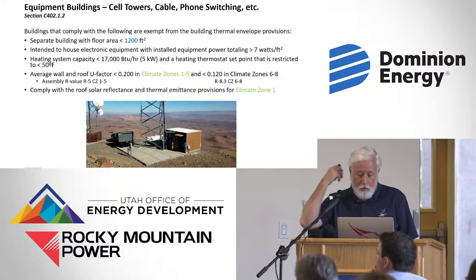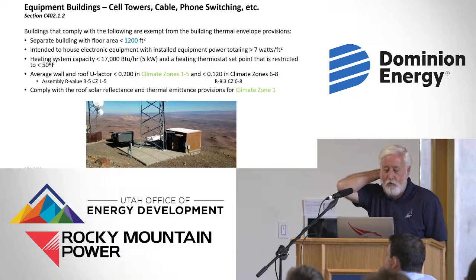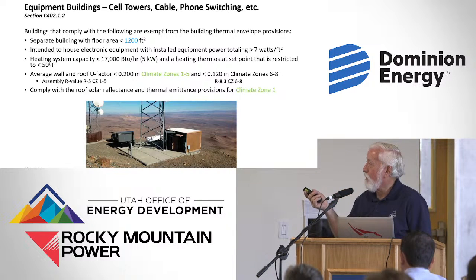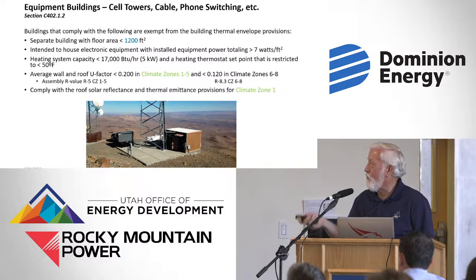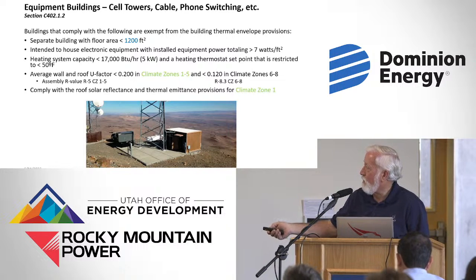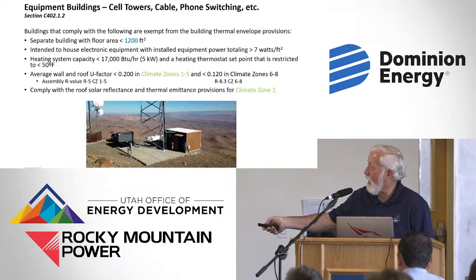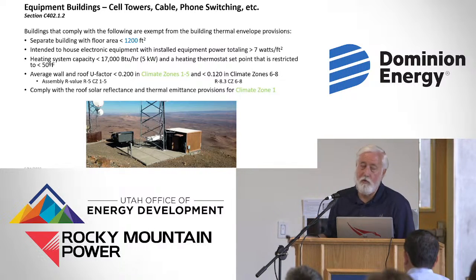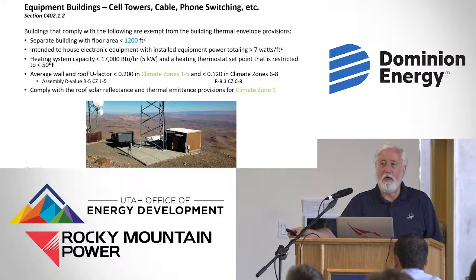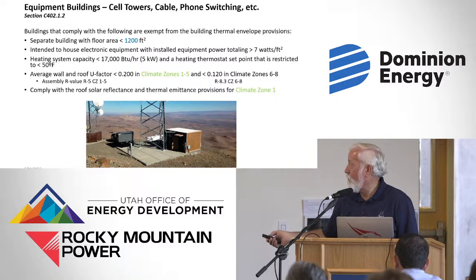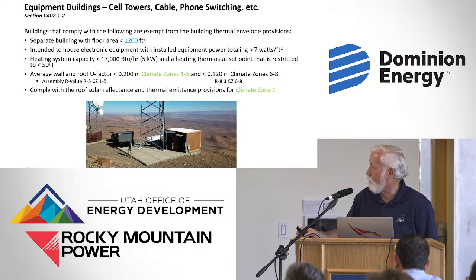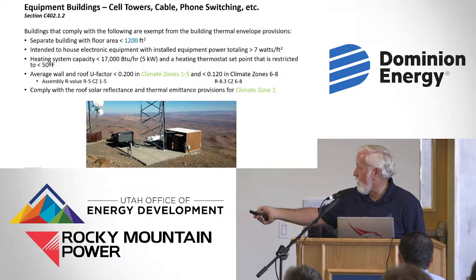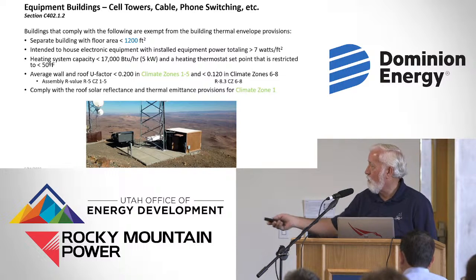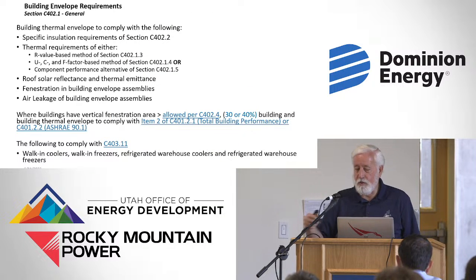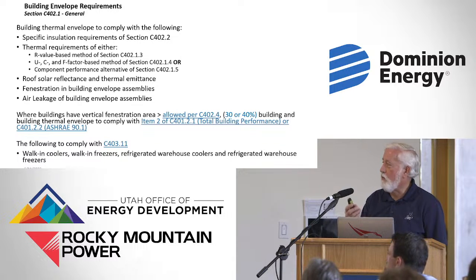Equipment buildings for cell towers and such, phone switching - basically what they're saying is they don't need much heat, they generate a lot of heat. Depending on your climate zone, an average wall and roof U-factor of 0.2 is basically an R5 envelope - that's not a lot. For climate zone 6 through 8, it's an R8.3, but you have to have a reflective roof as required for climate zone 1. So you don't have to do a bunch of crazy stuff insulating those, because they're producing so much heat, and the only thing you're worrying about is cooling it.